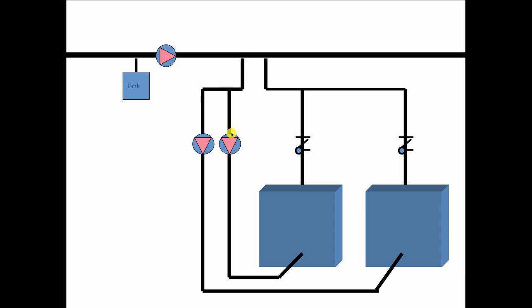So we always want to pump down, in this case, into the boiler and away from that common piping point, which is the secondary pump's point of no pressure change. It's their compression tank.